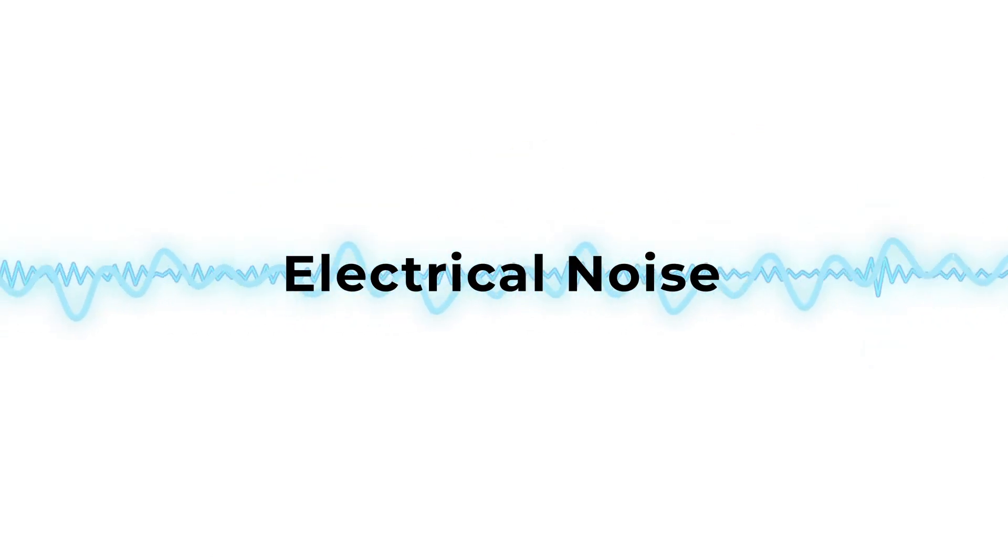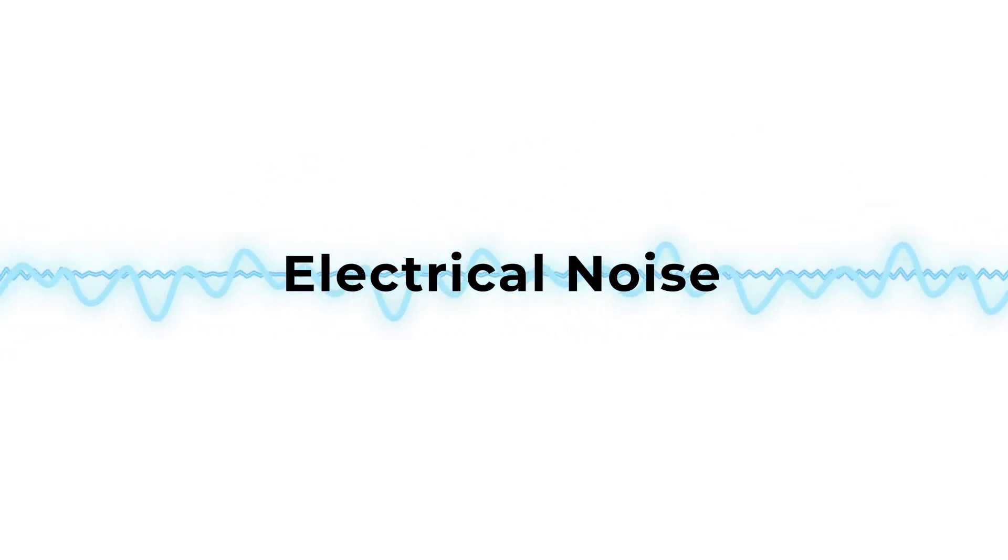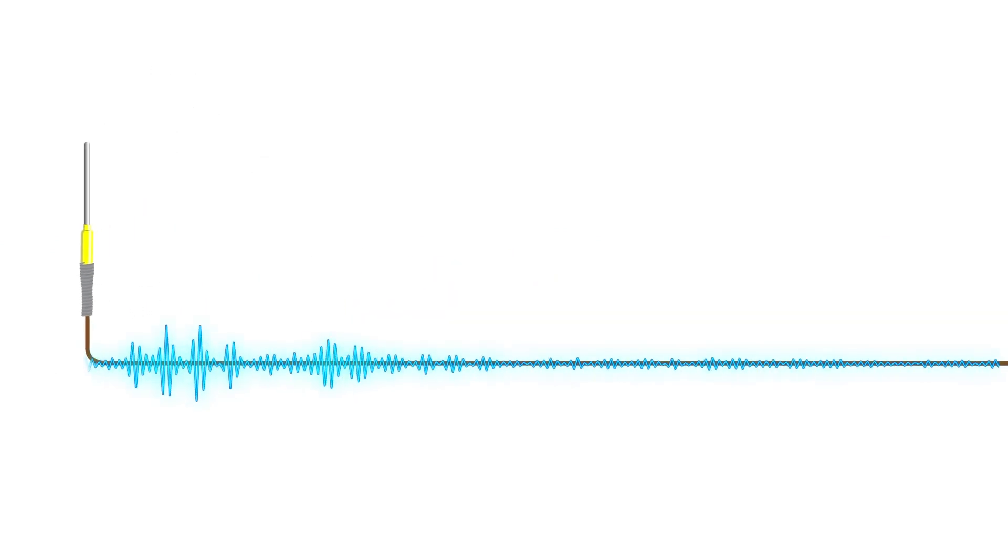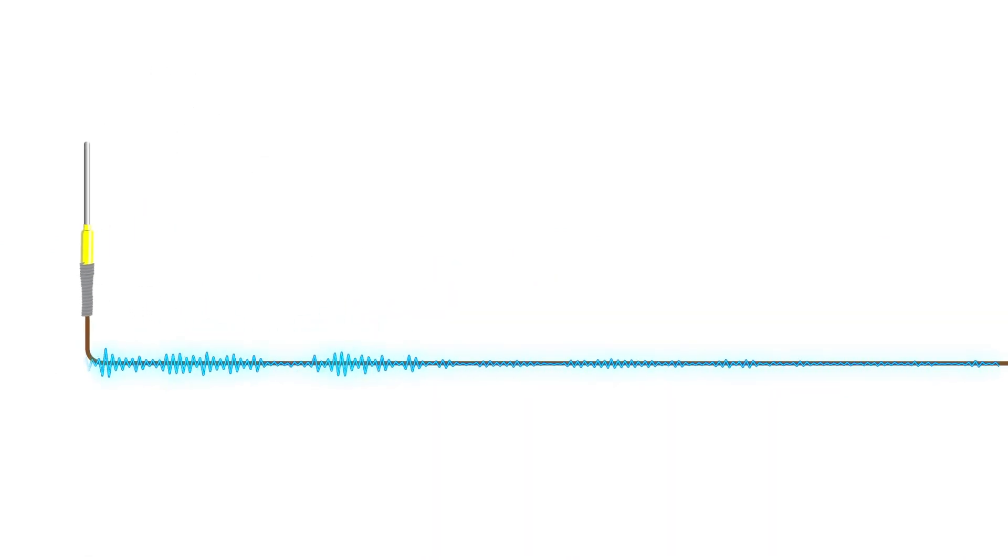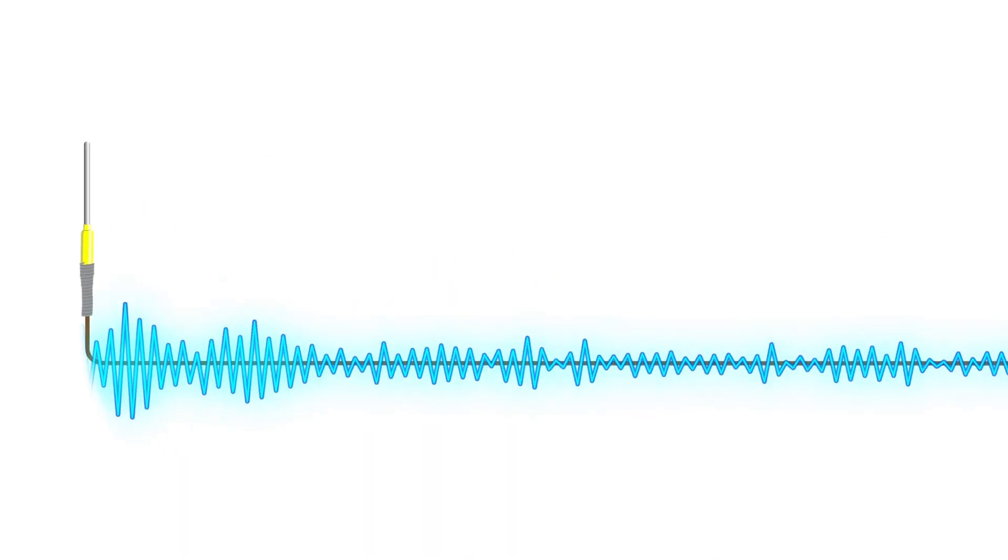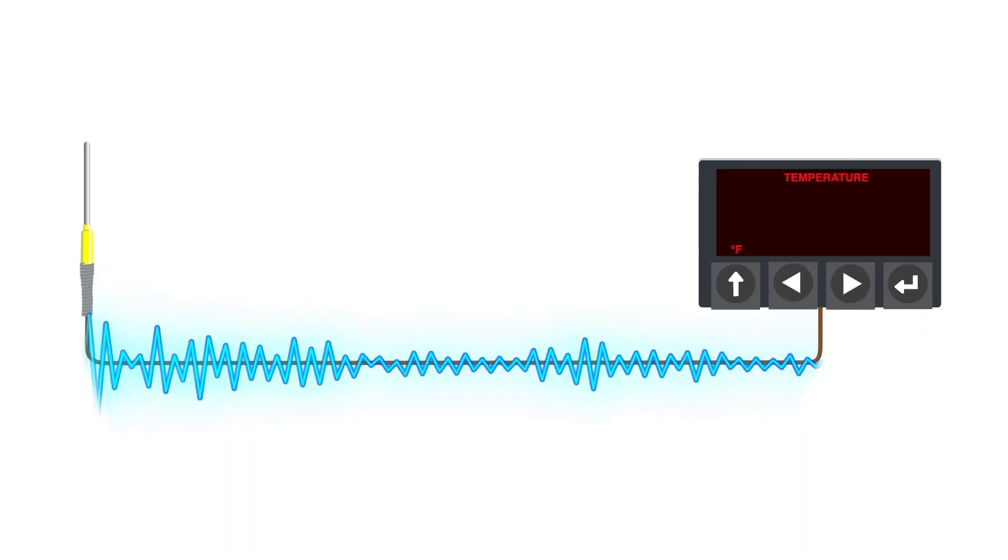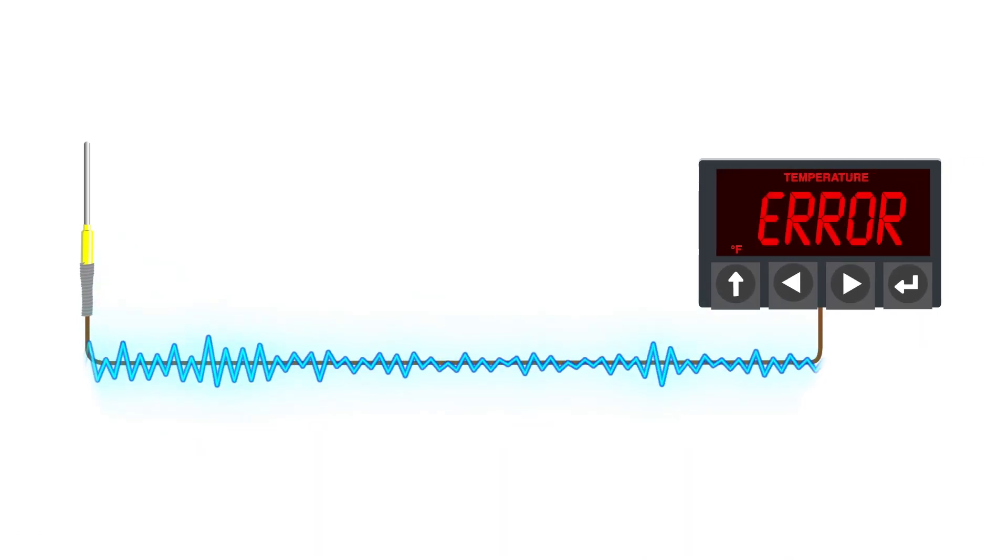Now let's look at electrical noise. A wire run can act just like an antenna, pulling in background electrical noise. The longer the run, the more noise they pick up, leading to signal loss and measurement errors.